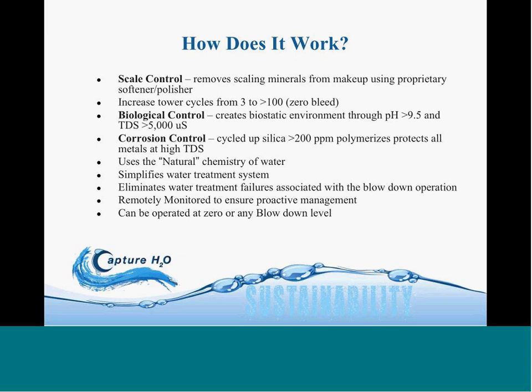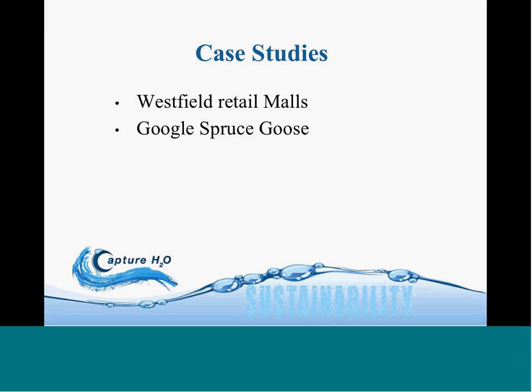Bacteria control comes from concentrating up that water so the pH rises to create a biostatic environment where bacteria can't survive in the water. Corrosion control comes from concentrating up the natural silica that's in the water. The groundwater happens to have higher silica than city water in LA, so it's actually a very good fit. The higher the silica, the better this program is. Ultimately, we're creating an environment where we're using the natural chemistry of the water. We just have to pre-treat it first before it gets in there. It simplifies the water treatment program, eliminates the failures associated with blowdown control, and of course we remotely monitor it so we can proactively manage the program and ensure that it continues to work. And it can be operated at any level of blowdown, up to 0 blowdown, so it gives the maximum water efficiency.